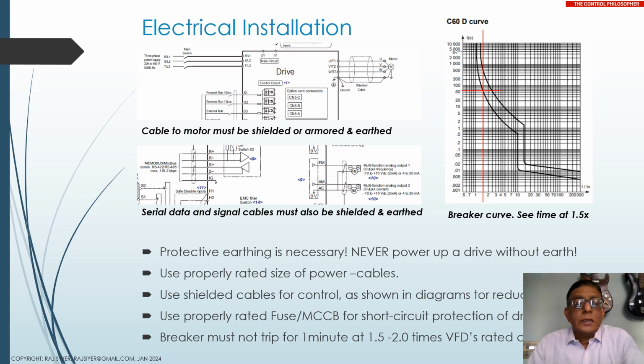I once again say that protective earthing is extremely necessary. You should never power up a drive without it being properly earthed. If the factory shed doesn't have an earthing connection, that is no excuse. I have seen factories like this. I have had them make earthing pits because we are using a drive. People are going to get a shock. All right. And the other thing is we have to use properly rated size of power cables, both those which are coming to power the drive as well as to power the motor.